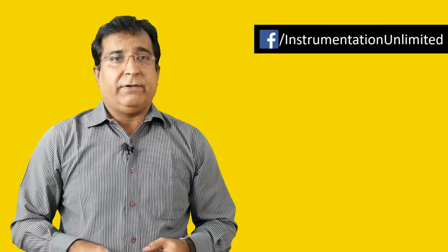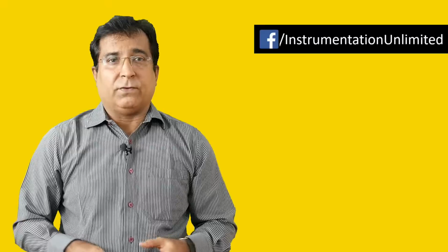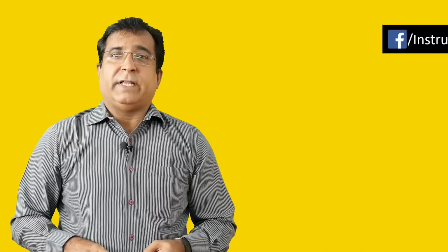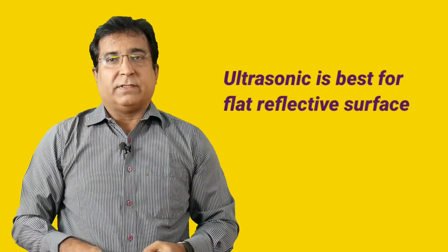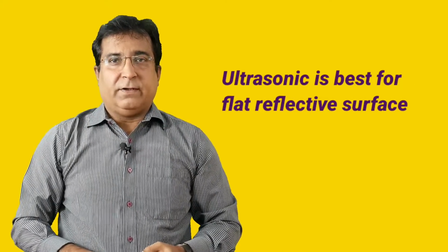Ultrasonic sound waves can manage and measure a material surface with an angle of repose. That's why ultrasonic is an excellent choice for solid level measurement. But it is important to note that using an ultrasonic sensor for solid level measurement reduces the effective range of the sensor by almost half. So this fact must be taken into consideration while selecting. However, the ultrasonic sensor works best when the reflective surface is flat, which is possible in liquids, and the liquid surface must be non-agitated, non-turbulent, and undisturbed. This is the fourth criterion.